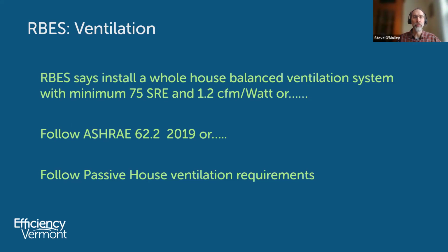Because what we find with using ASHRAE 62.2, which is a fine standard to use, your flow rates in some cases almost double. So you could be looking at, for a 1 bedroom apartment, it might be 60 CFM that ASHRAE 62.2 would prescribe. So when you think about adding up an extra 30 CFM per apartment, and you do that over a 30 apartment building, all of a sudden you've greatly increased the size of your equipment. So I steer people towards that simple formula when we're talking about the flow rates that are needed for apartments.